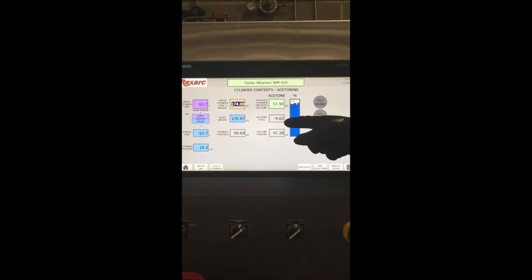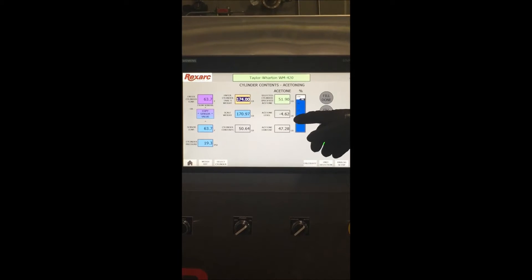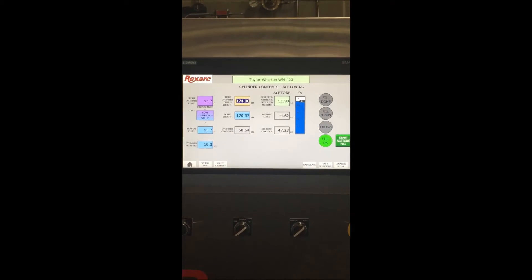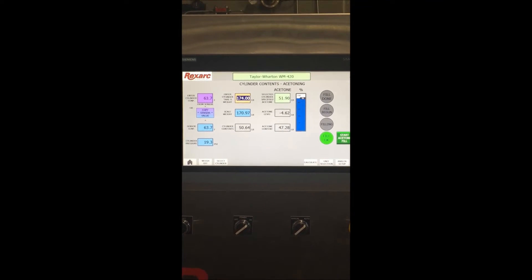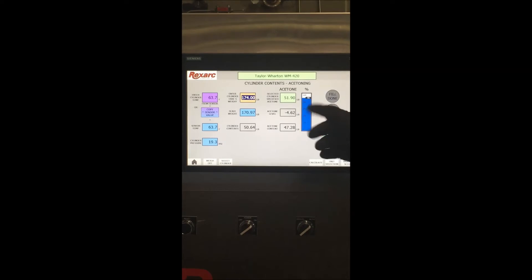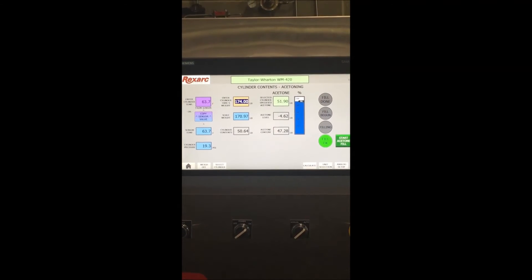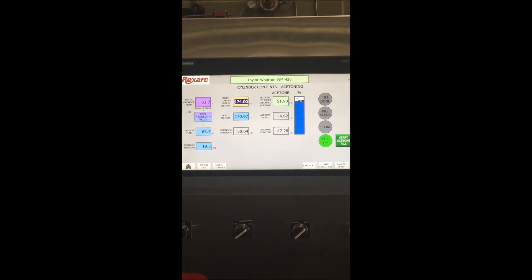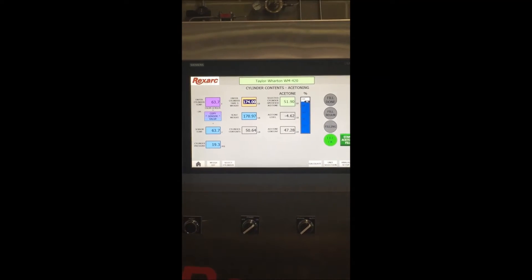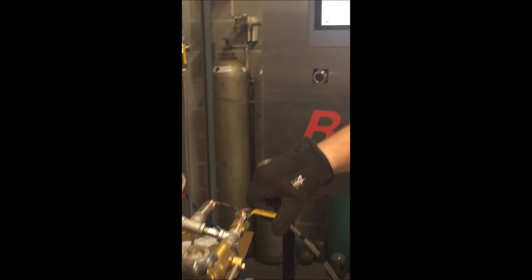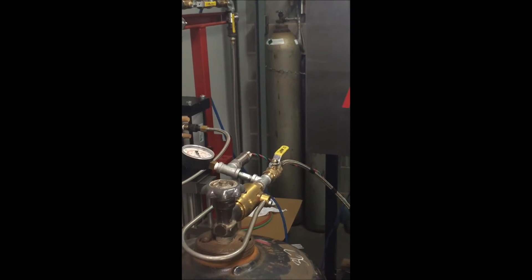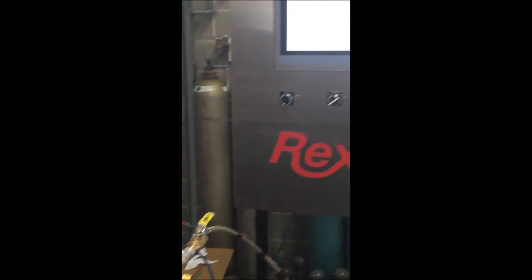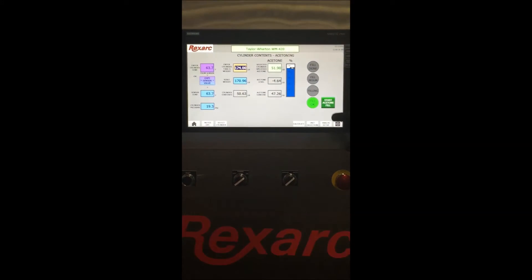If you look at the table here you will see that we are 4.6 pounds light on acetone which correlates into 91% of the correct amount of acetone in the cylinder. We will now open the hand valve on the acetone filling hose and begin the filling process by clicking here.